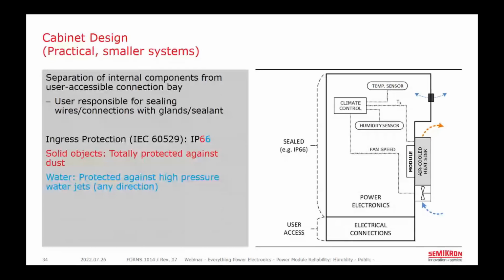So the incoming wires that the customer would connect to are in a separate compartment, which the installer is responsible for sealing, usually with a gland seal or conduit with maybe some sort of spray sealant or something like that. And the main compartment is sealed, perhaps to IP66 with some sort of gasket around here.